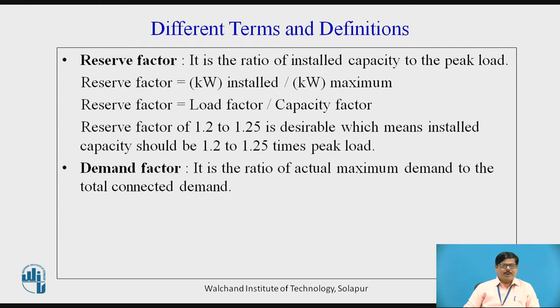The demand factor is the ratio of actual maximum demand to the total connected demand. Maximum demand is always less than total connected demand. In equation form, the demand factor equals kilowatts maximum divided by kilowatts connected.